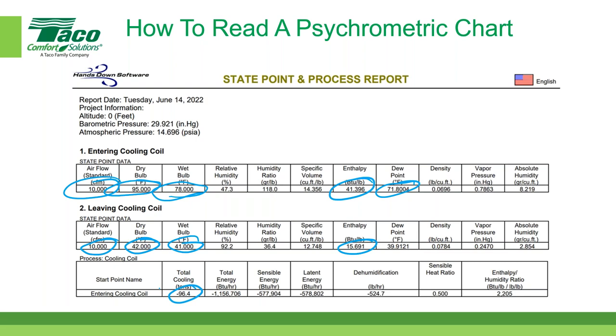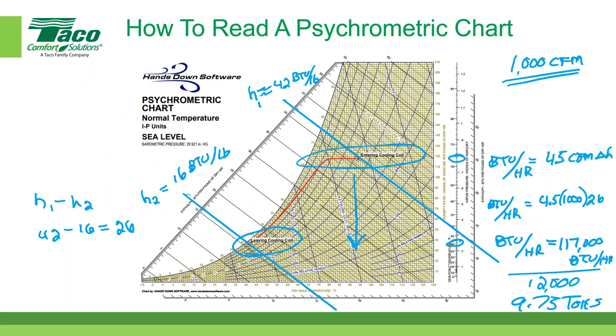Cameron's asking, why did you divide by 12, actually 12,000, to get the tons, correct? Oh yeah, way back here, the original value is 117,000 BTUs per hour, and I divided that by 12. I should have written it over here somewhere. Let me put it up in the left-hand corner. So it's 12,000 BTUs per ton-hour. That's the conversion between BTUs per hour and tons. Hopefully that answered that question.